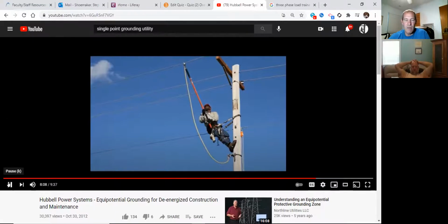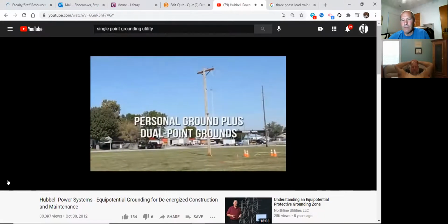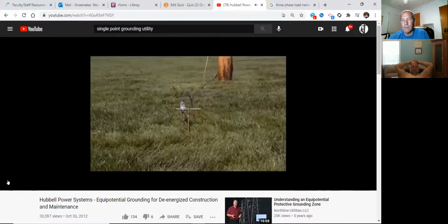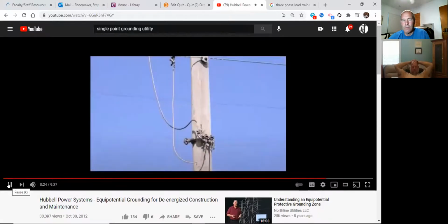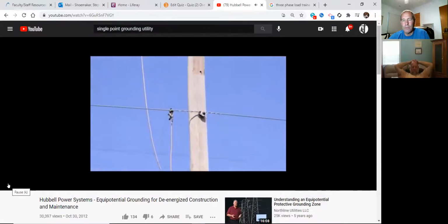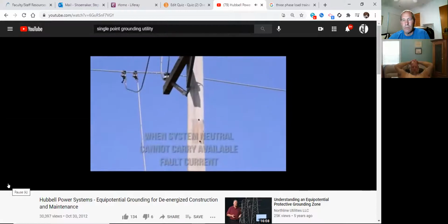Now he's protected to perform the maintenance this service call required. He's allowed to do maintenance on 1 phase, not all 3. Right. Protected by a personal ground here, plus dual point grounds at the 2 adjacent poles. On a system with a neutral too small to carry available fault current, connect 1 lead from the cluster bar to the neutral and another lead from the cluster bar to the first phase.